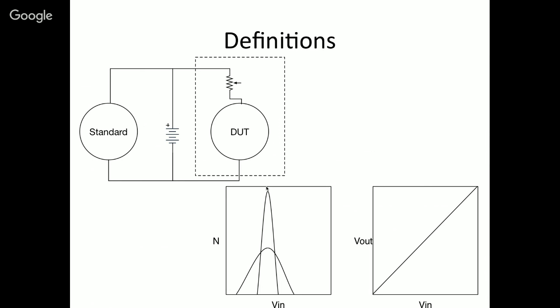Now, on the bottom center, you see a pair of graphs here. You see this Gaussian curve, this large, shallow one, and then you see this thinner, taller one. The taller one is that of the standard, which is usually going to have a higher accuracy and precision to it, whereas the shorter, more spread out one is usually the device under test. If you're doing your testing right, then you should have a more accurate device as your standard, the thing that's already been calibrated by somebody else, and which is instilling traceable calibration, we'll get to that in a moment, into the device under test.